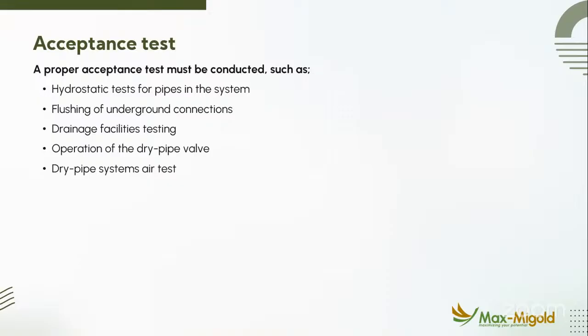So the hydrostatic tests for pipes, you flush the underground connection, to ensure that there is no blockage or obstruction in the pipe if you are having the hydrant pipe. And you ensure that you test the pipe to its maximum pressure, same thing as the pump. But for the pump, we test the pump to 50% above its nominal pressure, its normal operating pressure, to ensure that the pump can actually fire up if it's a new pump. If it's not a new pump, please don't bust your pump. Just test your pump based on the operating pressure.